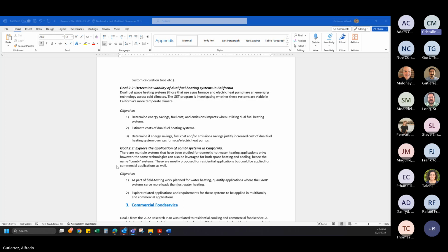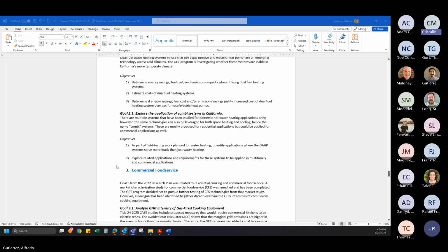The last goal under HVAC is to explore the application of combi systems in California. A combi system, as we call it here, is a system that does gas-fired water heating and gas-fired space heating, so it would be a hydronic space heating system combined with water heating. One of the GAHP manufacturers makes a system that can take the heat from a chilled water loop and transfer it into a hot water loop to heat either domestic hot water or space heating hot water. That unit is something we want to test. We haven't been able to find any publicly available test data on it, but because it requires a concurrent cooling and heating load, the types of buildings we can put it in are somewhat limited. So we've been focused on recruiting for the domestic hot water application, and once we get those stabilized, we want to recruit for this combination system application and do a field study on that.